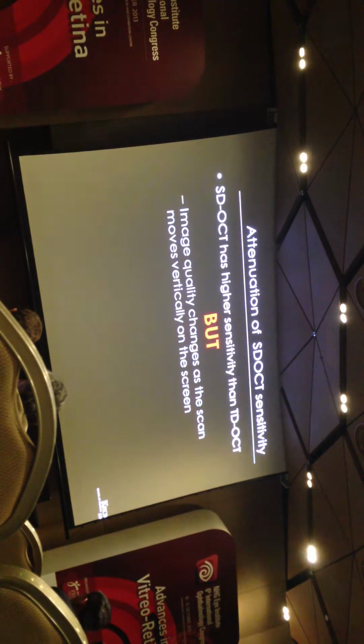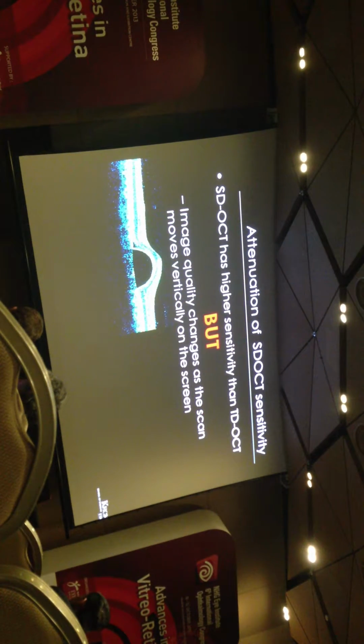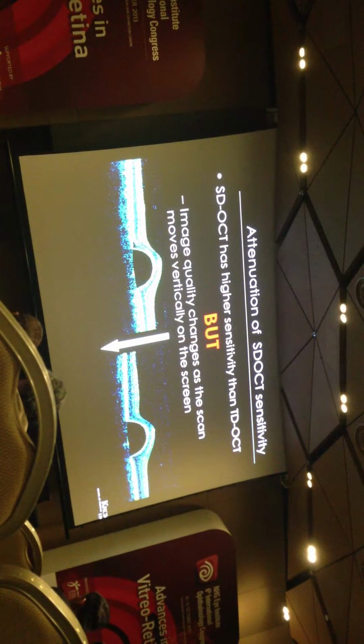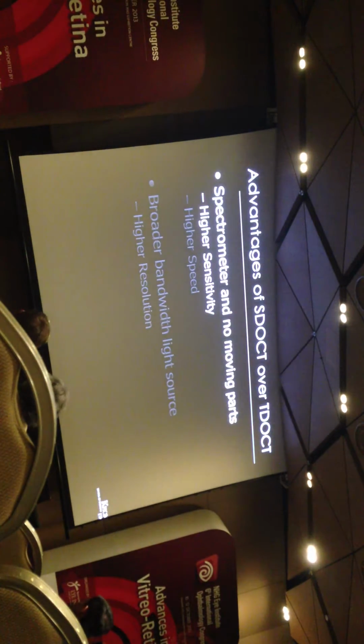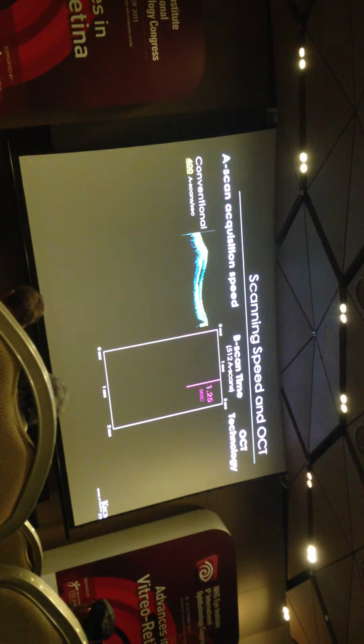So that higher sensitivity is great, but one of the caveats that I pointed out yesterday as well is that remember that spectral OCT is really sensitive as you're close to the zero delay, which usually is set to the vitreous side. It's the whole concept of why enhanced depth imaging came to be, which is basically to say let's move the most sensitive side towards the choroidal side of things. But the point is that there's this fall off, and again, one of the key advantages of the swept source technology. And then, the other major advantage we've talked about a little bit is higher speed.